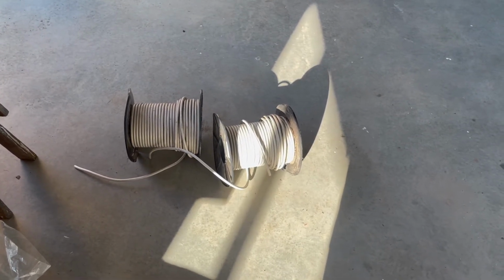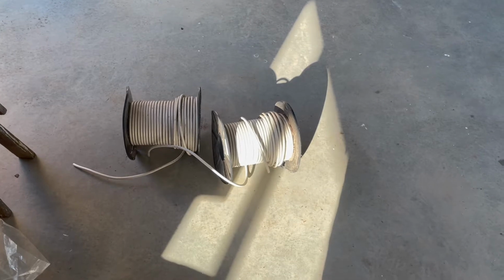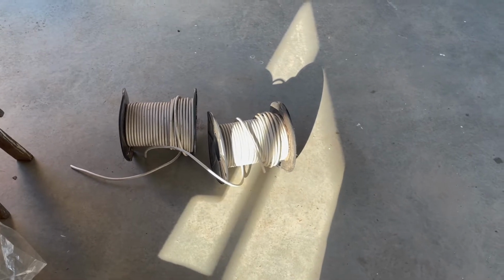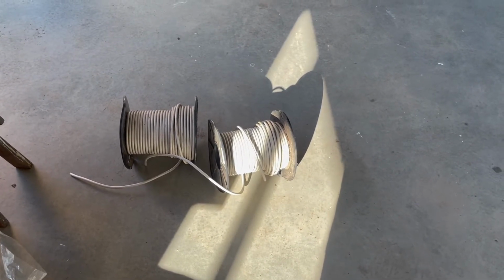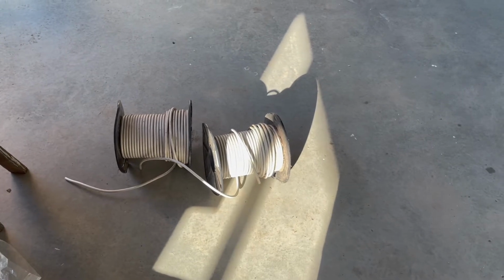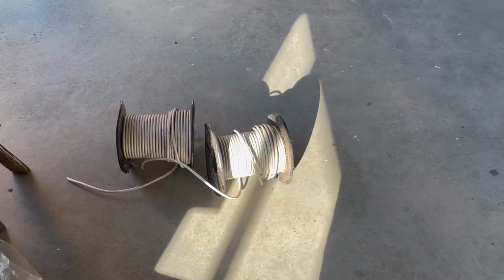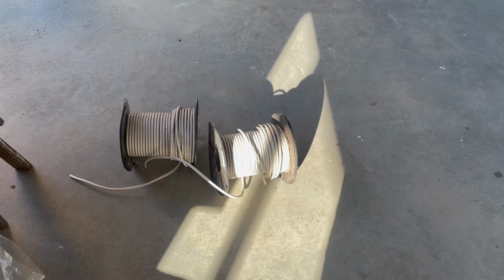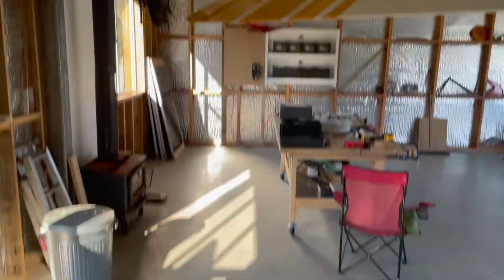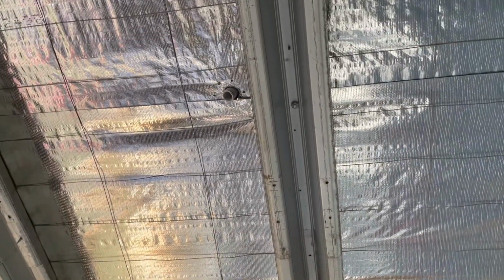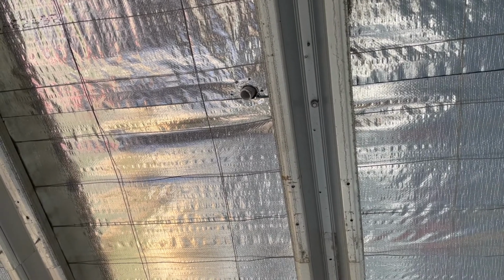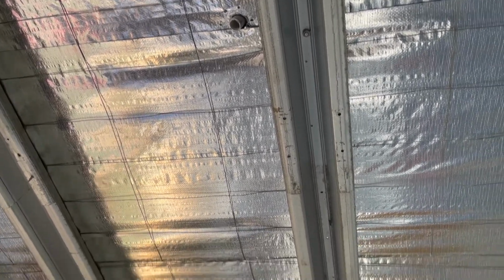Here on the floor I've got 2 rolls of 16mm builder's wire. It's double insulated. If I peel off the outside insulation layer, which is white, one's coloured red and the other's coloured black. I'm going to roll them out on the floor to the base of the power board, tape them all together and get a nice straight line of wire, and then I'm going to thread it up along the roof battens and up through the roof penetration, which is here, and that'll put the wires up to the solar array. So I'll go ahead and do that now.